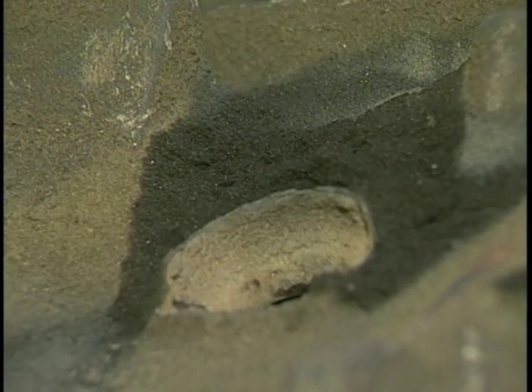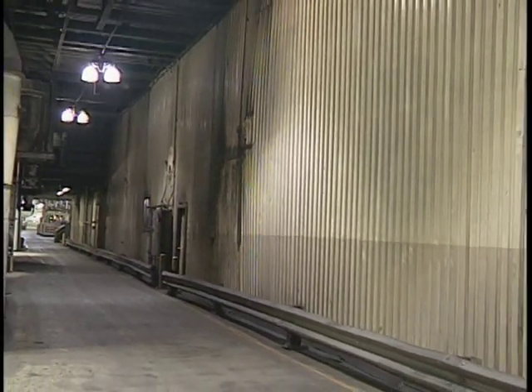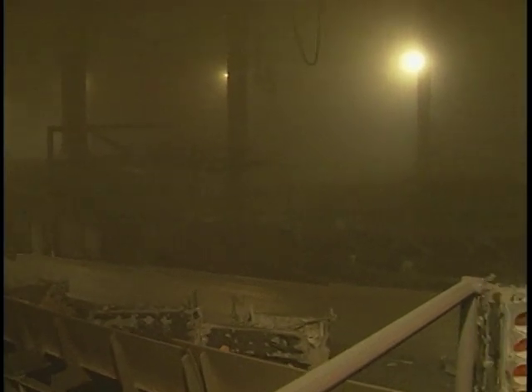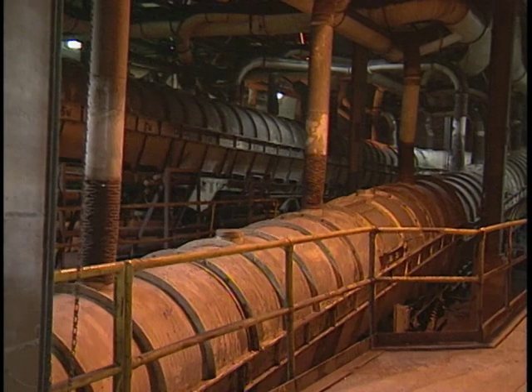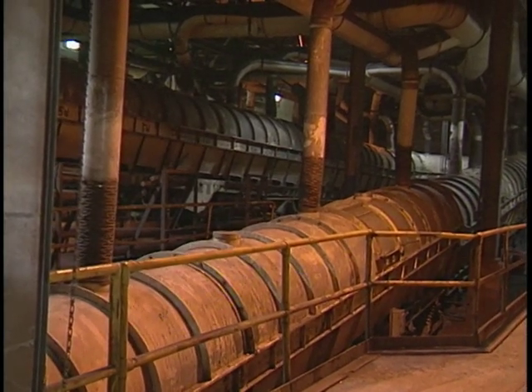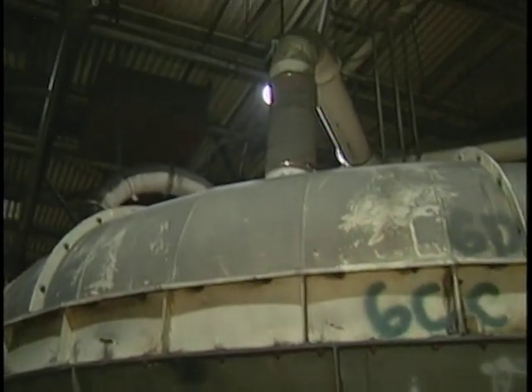The cleaning of formed castings, which contain dry sand, presents the biggest risk of silica inhalation. Again, isolation and ventilation are the keys to protecting the worker. This structure is a completely enclosed shakeout operation. As castings move along the conveyor, the loose silica is shaken from them. Personnel do not enter this room, and it is ventilated so that the dust does not escape into work areas. Likewise, this shaker pan is completely enclosed as it shakes the castings free of silica. Again, the necessary exhaust is present.